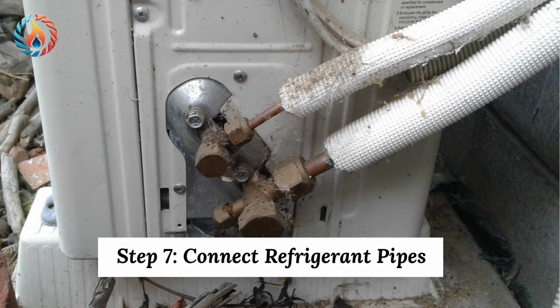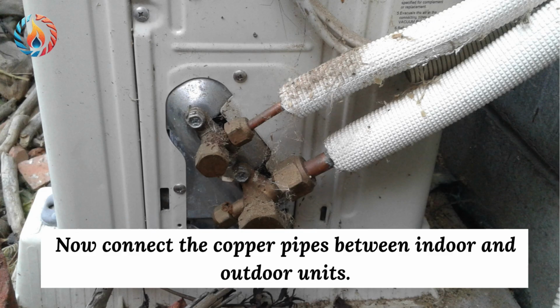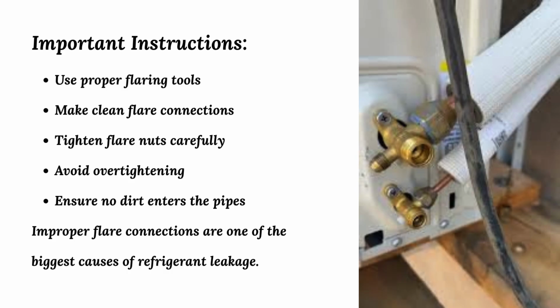Step 7. Connect refrigerant pipes. Now connect the copper pipes between indoor and outdoor units. Important instructions. Use proper flaring tools. Make clean flare connections. Tighten flare nuts carefully. Avoid over-tightening. Ensure no dirt enters the pipes. Improper flare connections are one of the biggest causes of refrigerant leakage.